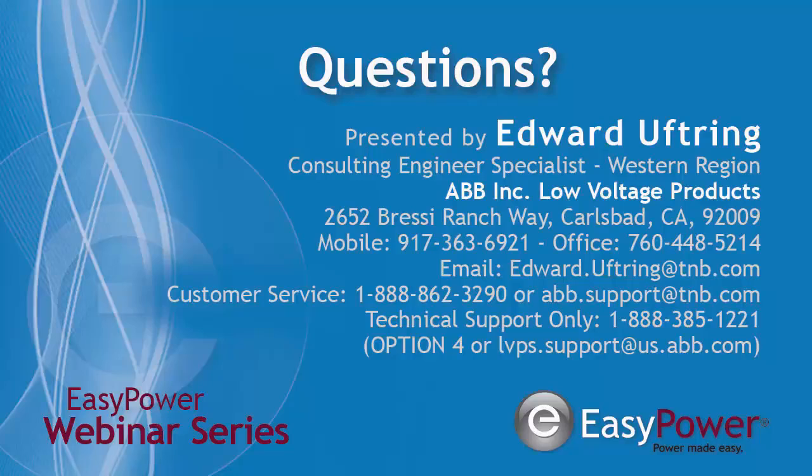Can trip settings be changed while live? Yes, they can be, but we don't recommend you doing it. The best way to do that is with an electronic trip unit so that you're not near the breaker flipping that dip switch.